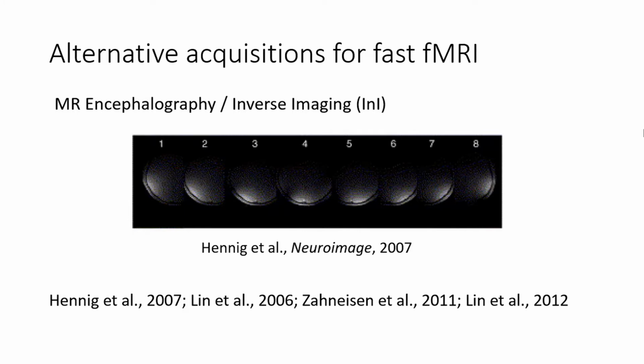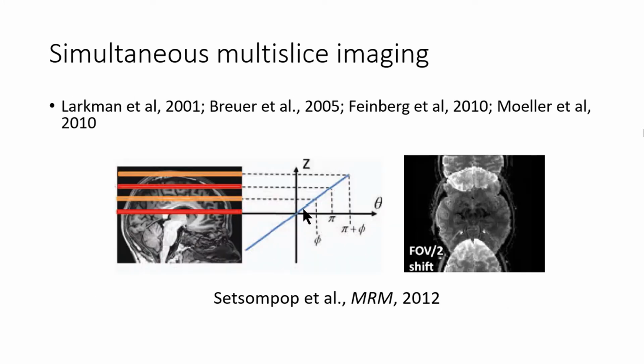And so what's become now very widespread since this development of simultaneous multi-slice imaging is the use of SMS to acquire multiple slices simultaneously and thus achieve very fast imaging. So instead of taking the time to step through your slices one at a time, if you now were to acquire, for example, in this example, these two orange slices simultaneously, you end up with an image where the slices are overlaid onto each other, but it's actually possible to go back and untangle these two images.